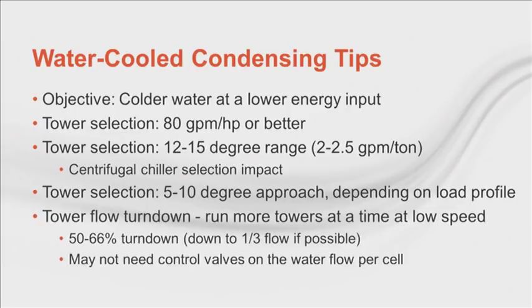And finally, flow turndown. If we have a good enough flow turndown, we can flow one chiller across two towers. That would be a 50% turndown, which is the minimum code requirement. Even better would be a 66% turndown, or 1/3 of the flow, so we could run one chiller across 3 towers. You may even be able to eliminate water flow control valves if you can always run all the towers.